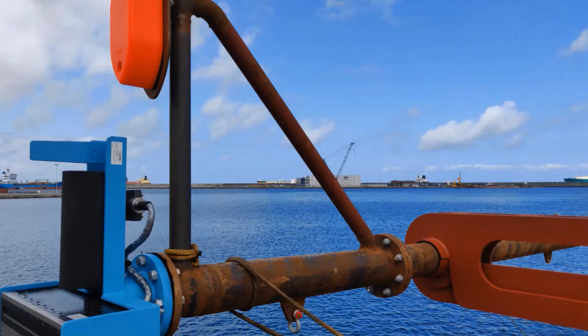There is a limit on any transducer to the amount of energy it is able to discharge. A too high voltage for a prolonged period can build up a very high acoustic pressure and can cause cavitation in the system. Now, due to this cavitation, acoustic pressure is not effectively getting transmitted, and it can cause vaporization of the water molecules on just the face of the transducer, which can form gas bubbles on it and even damage the transducer itself.